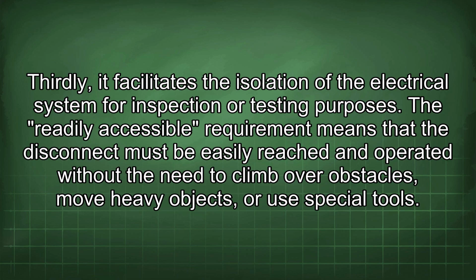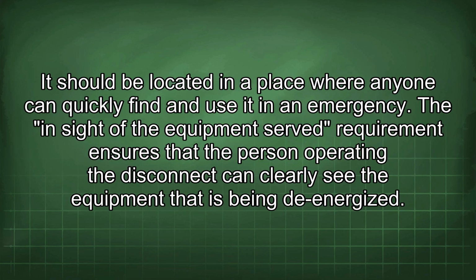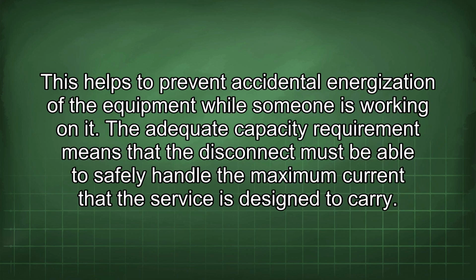The readily accessible requirement means that the disconnect must be easily reached and operated without the need to climb over obstacles, move heavy objects, or use special tools. It should be located in a place where anyone can quickly find and use it in an emergency. The within-sight-of-the-equipment-served requirement ensures that the person operating the disconnect can clearly see the equipment that is being de-energized. This helps to prevent accidental energization of the equipment while someone is working on it.